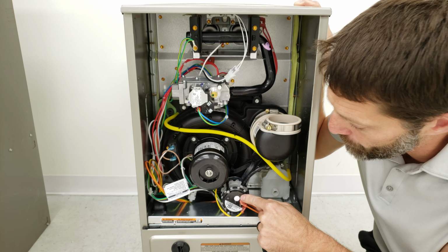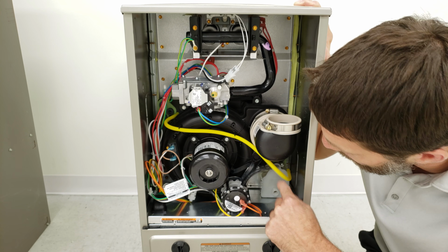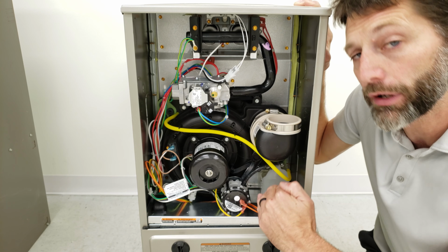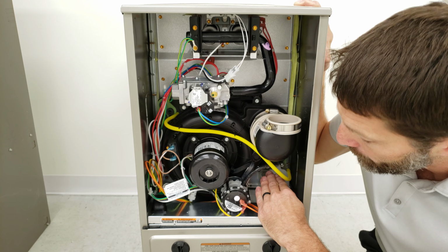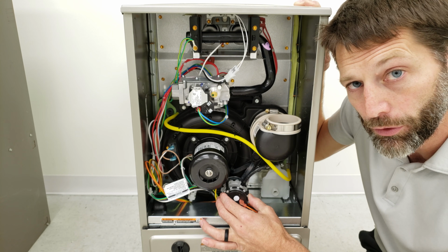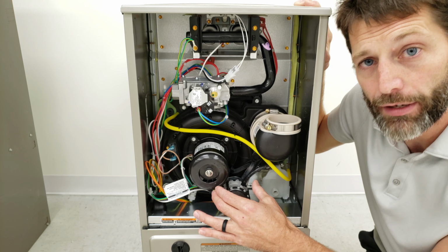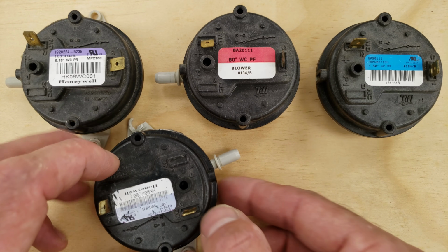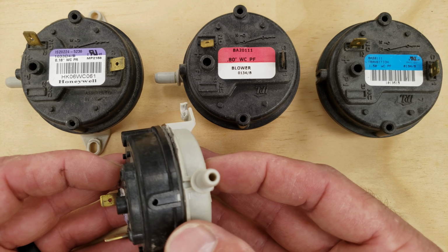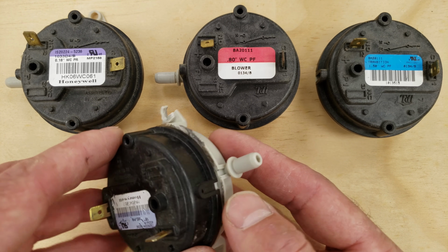The other thing is this pressure switch is going to monitor the condensate line and condensate trap in case there's a clog. If the water level rises due to a clog, it's going to open up the electrical circuit, and so these are acting as safety devices. Pressure switches work on a differential of pressure. So this is made up of two air chambers.